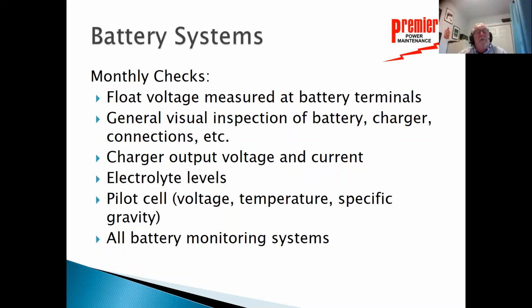Even after the design and the install, again, it's the most important piece of equipment that you have in your electrical system. There are monthly checks that need to be done. And that's one of the first things that companies tend to knock out of their budget, these monthly checks. Float voltage, measure the battery terminals, pretty simple, doesn't take a lot of time. A good visual general inspection of the battery and the charger, make sure everything's working there, make sure that there's no leaks on the ground. Make sure there's no ground on that battery system.